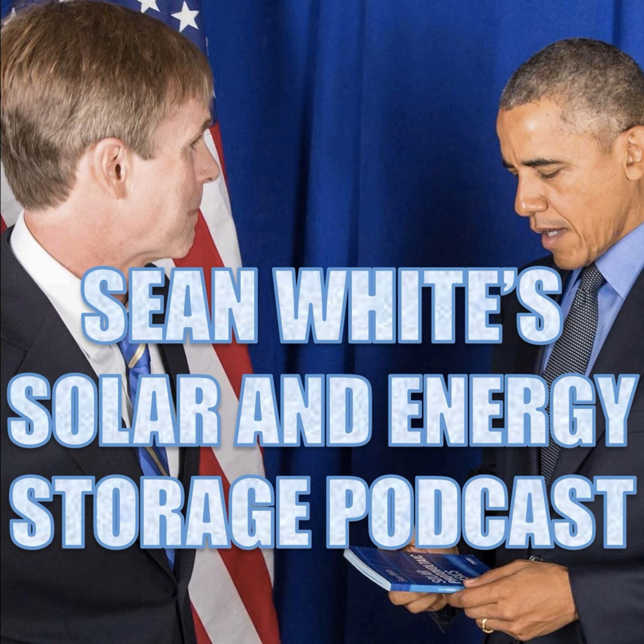When you look at lithium ion, it's kind of the same trick the PV inverter manufacturers use with their MPPT efficiency. Every inverter company uses a voltage range that makes their maximum power point tracking look the best. So when you look at batteries, lithium manufacturers will tell you that you can use 100% of the capacity, or maybe 90% or 95%. So there's this usable capacity versus total capacity.